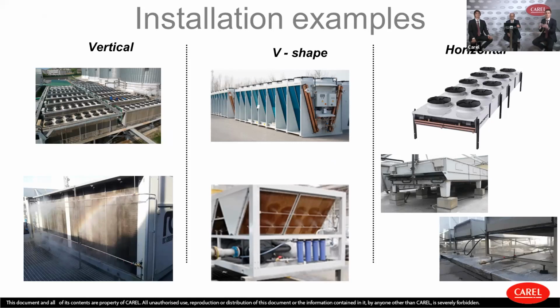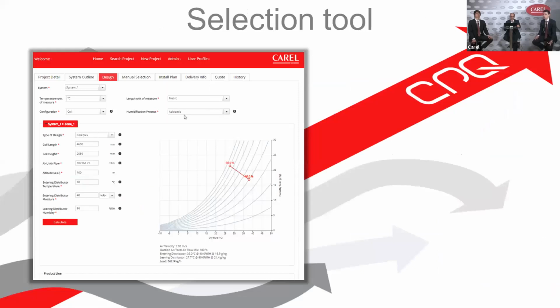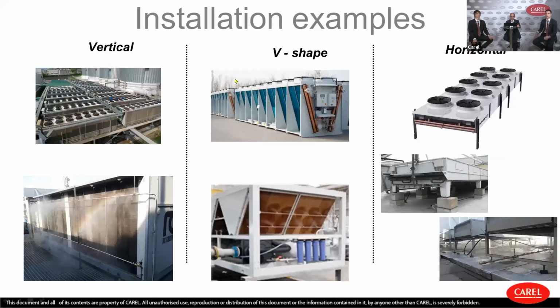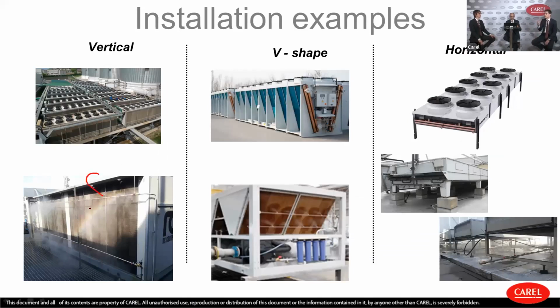In vertical, we place the manifold literally in front, and usually we spray water counterflow so you don't damage the fins or the heat exchanger. But it may be different: for example, in this shape the manifolds are placed in front of the heat exchanger as well, but we spray gray over gray, so it's not very easy to see, but it's like that. And as I was saying, in the V shape you can spray on the fins, for example, in this case, because maybe the water was treated or checked. So we get the double effect we were speaking about at the beginning.